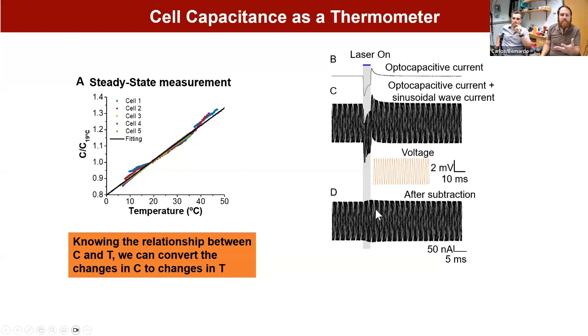At the same time, as a validation, we use the measurement from the pipette. We call this method of measuring the temperature using capacitance capacitance-based temperature measurement, or CTM, okay? And you can see that there's a difference between the measurements using the pipette and the capacitance. This difference is due to the distance between the membrane and the pipette. Even if we try to put the pipette very close to the membrane, we're still a couple of micrometers away. Due to how the heat diffuses in the system, this generates a couple of degrees of difference. So this method gives us the temperature right where we want to measure, which is the membrane, where we're going to do our recordings.